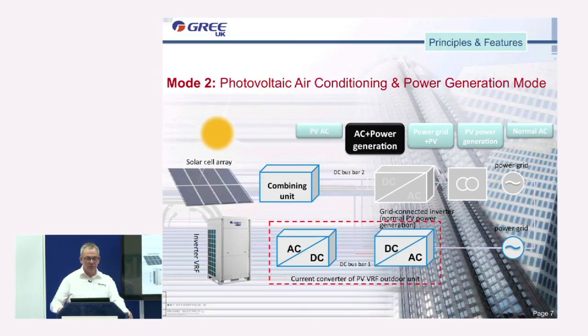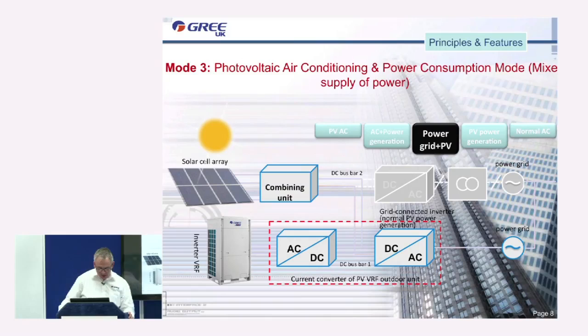So that's mode 1. Mode 2 is when we can generate power and we have enough power to run our machine, but we have generated also an excess of power which we can then direct back to the grid. All handled by the DC bus bar and the control management within the PV VRF unit. Mode 3, this is when PV generated power is not sufficient for the VRF consumption, so power is then automatically streamed from the grid. So there is no additional switching, there are no additional components required for this. The management of the voltage in the system and the power generated is such that we can just utilise the power that we are generating for our unit, and if we need some more additional power, then we can take that from the grid.